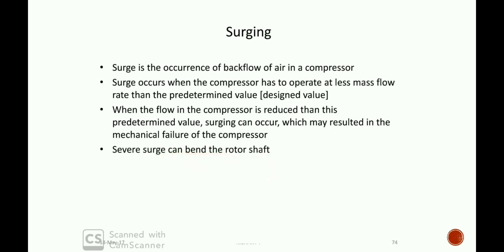A severe surge can bend the rotor shaft. Normally, the compressor shows pulsating flow and backflow. This leads to high vibration, pressure shock, and overheating, which results in mechanical failure of the compressor. Surging can also be described as a phenomenon of pulsating air flow through the compressor with high frequency.